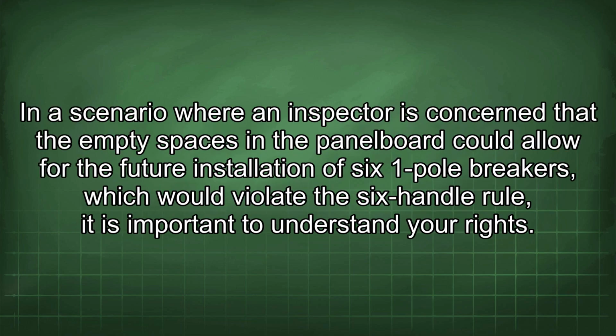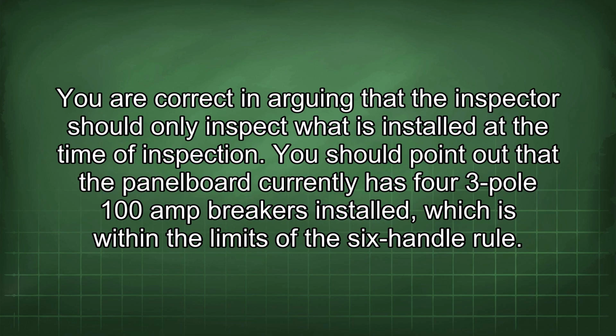In a scenario where an inspector is concerned that the empty spaces in the panel board could allow for the future installation of 6 one-pole breakers, which would violate the six-handle rule, it is important to understand your rights. You are correct in arguing that the inspector should only inspect what is installed at the time of inspection. You should point out that the panel board currently has 4 3-pole 100 amp breakers installed, which is within the limits of the six-handle rule.